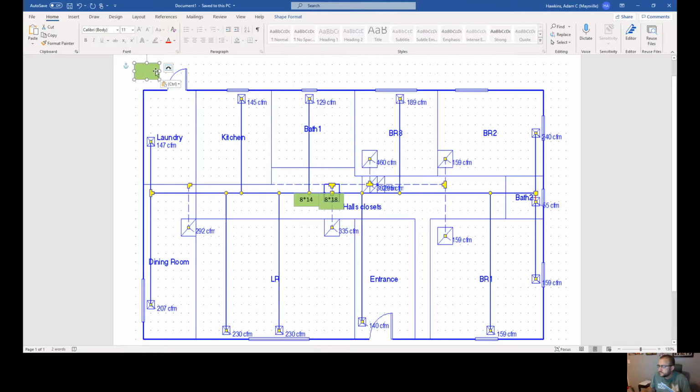All right, next piece. If nothing comes out of any of these individual pieces, then the duct size doesn't change. But in this case, it looks like most pieces have something out of them until we get to the very end. Speaking of the very end, you don't have to run your duct all the way to the end if you can reach it with your flex. This one runs all the way to the end of the house. You don't have to do that. As long as you can reach it within a small distance, you can stop short of the house. So we may actually do that on this.